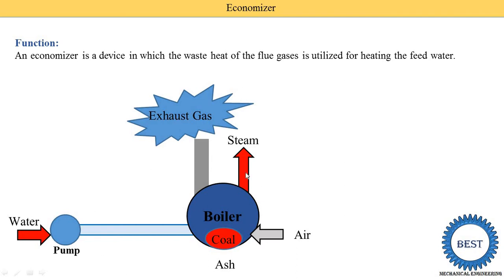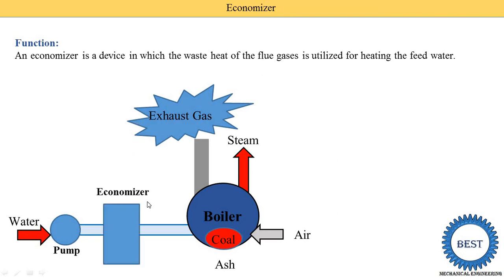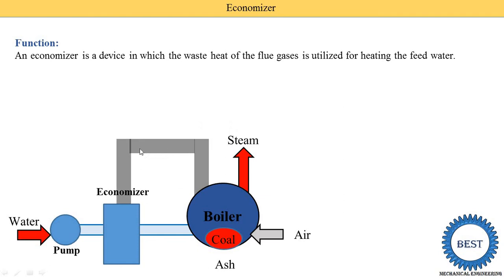Now, suppose we want to heat the water — we install one economizer. If we need to heat the air, we put one air preheater. And if we want to heat the steam, we put one superheater. All three components are supplied with the exhaust gases, meaning heating is done by using the exhaust gas. Water from the pump comes into the economizer, and this exhaust gas is also supplied to the economizer, so this waste energy is utilized to heat the water. Then, we are able to achieve higher temperatures of the steam. After the exhaust gases leave this economizer, they are supplied to the air preheater, then to the chimney, and go to the atmosphere.